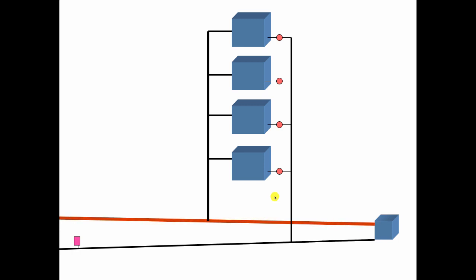So let's see what happens now. Steam comes up, goes down the end of the main and starts to climb the ladder. But since that trap's failed, it crosses into the return. Oh look, now it's in the return. Now it's in the return downstream of the trap. Oh, it just shut the air vent here. So both lines are filled with steam and everybody above this guy has no heat. Now this is one of those things that's true of life. The guy with the bad trap will always have heat. He will never call you. It's everybody above him. They'll have no heat. So you won't go to this guy. You'll go to these people.